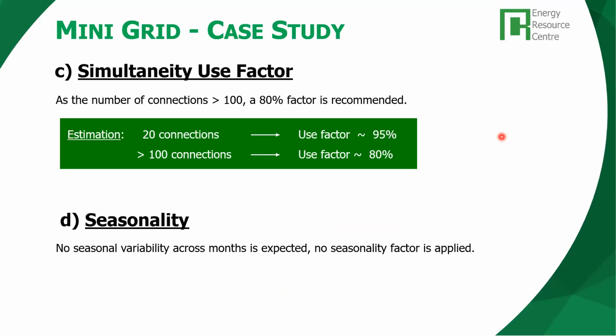For the use factor, because we have a number of connections above 100, we recommend at least a use factor of 80%. So this is what we take. If we had a smaller number of connections, we would be taking a 90%, 95% use factor. In this case, we have 137 connections. We can take 80% as the use factor. So we will need this factor when we scale down the aggregated demand of the community.